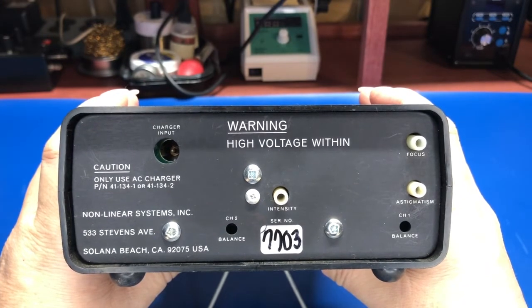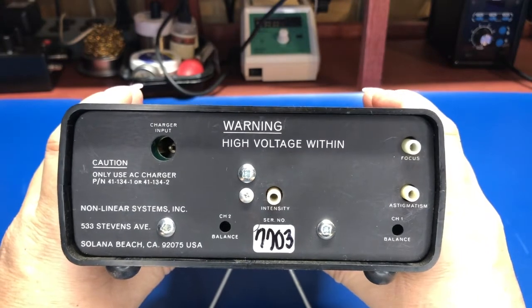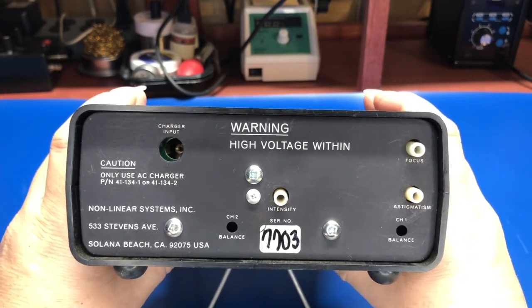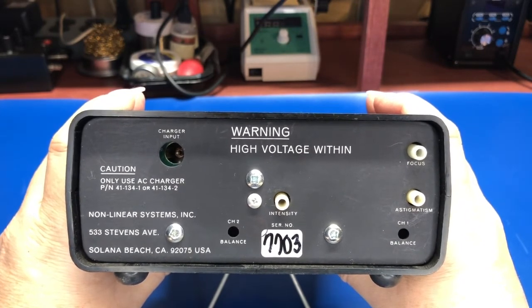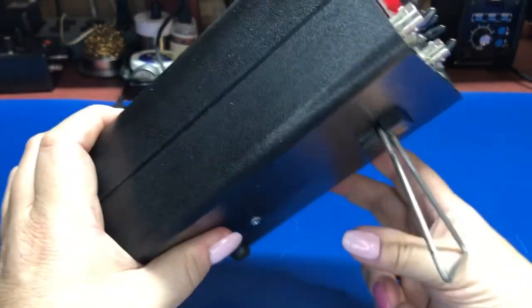Around back I've got the input for the charger, adjustments for intensity, focus, astigmatism, and you can get a channel one and two balance — that's just to tweak the front ends a little bit. And you can do that without having to open it up. All the other adjustments you have to slide it out of the case to access.